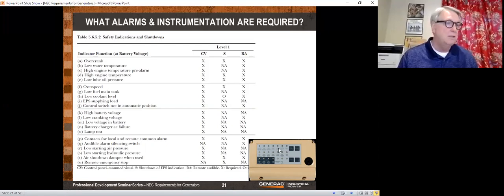When somebody buys a generator, puts it in, the inspector comes out and says, well, where's the remote annunciator? And they call us and say, hey, we need a remote annunciator. And we tell them, there is no remote annunciator. You didn't buy an NFPA 110 control panel, and it's not available. You've got to buy a new generator.